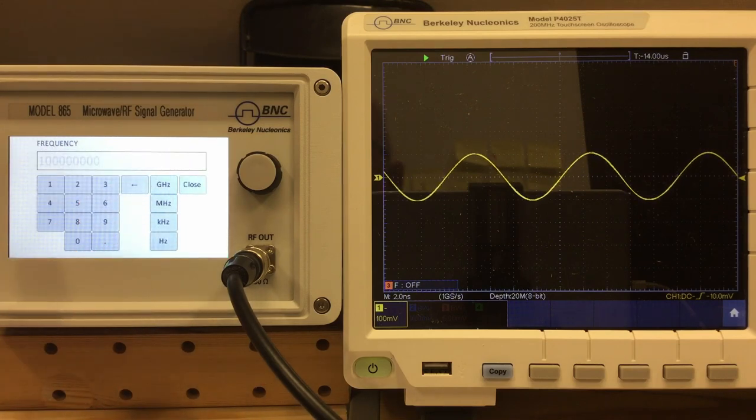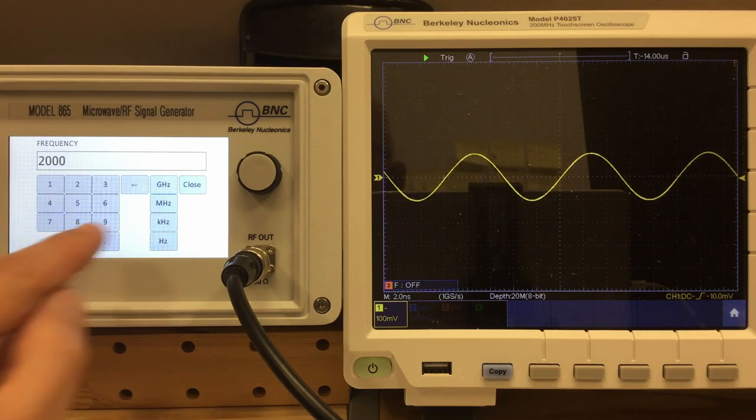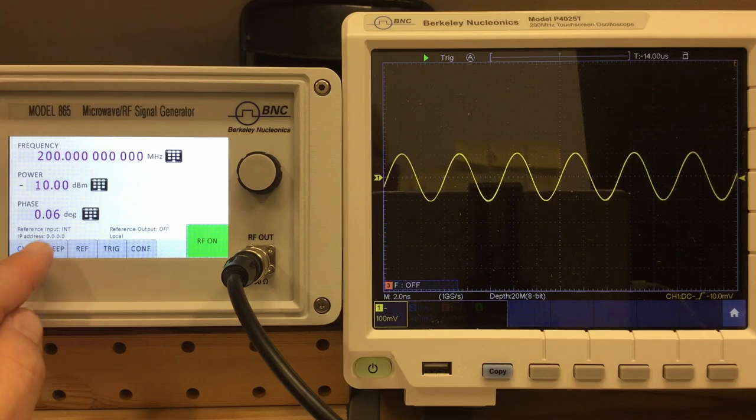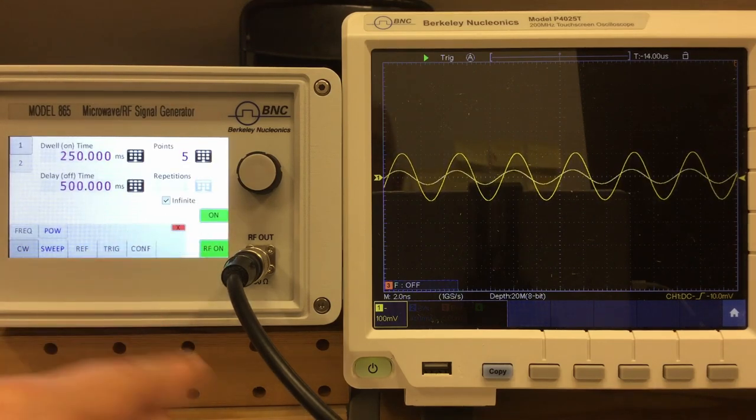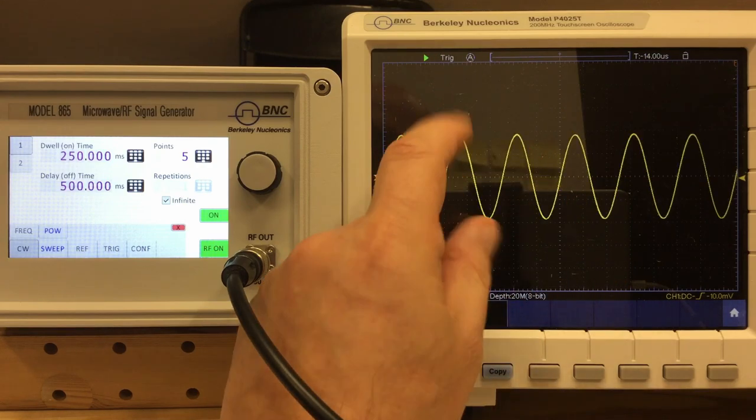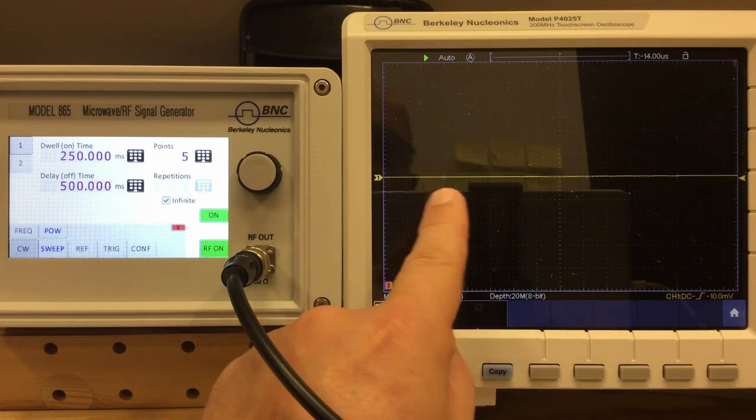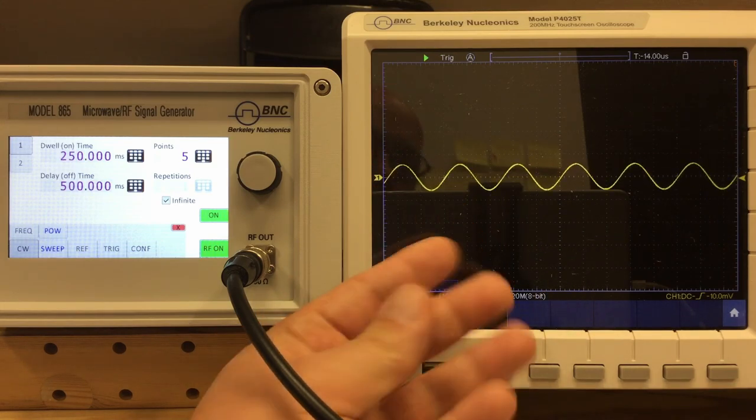And when we switch that on, we see with a constant frequency, our level rising of the signal. In between the signal goes to zero and the frequency of the signal in that case is set here in the continuous wave menu. So if we go here, for example, to let's say 200 megahertz, we go back to our sweep. Then we amplitude modulate, step through different signal levels at a 200 megahertz signal. That's it.